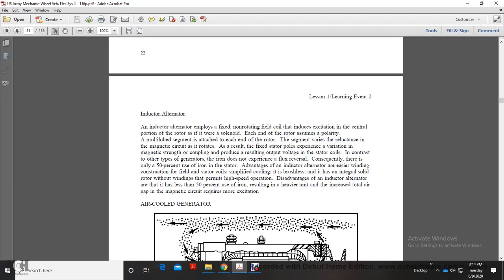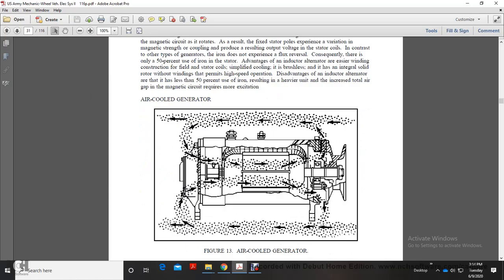The advantages of the inductor alternator are easier winding and construction of the field and stator coils, simplified cooling, it is brushless, and it has an integral solid rotor without windings that permits high speed operation. The disadvantages of the inductor alternator are less than 50% use of the iron, resulting in a heavier unit, and an increased total air gap in the magnetic circuit, which requires more excitation current.